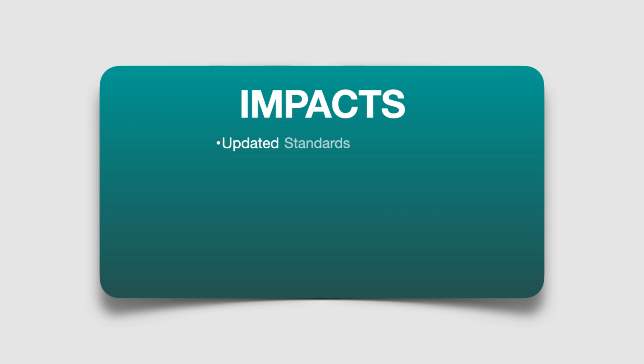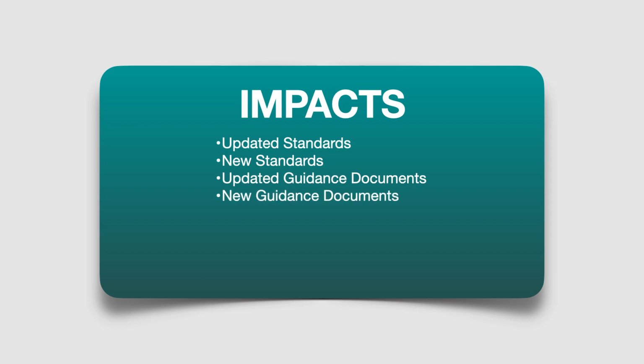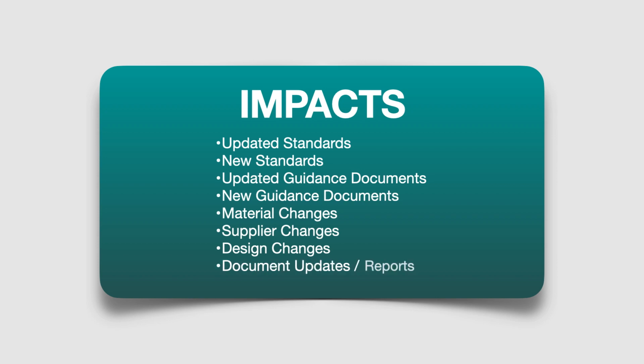As a manufacturer of medical devices, however, we must constantly prove conformity with Annex I. And there are constantly impacts that trigger proactive action. Standards are revised from time to time. Completely new standards come out which, as a manufacturer, I have to take into account. Guidance documents and best practices are also revised or newly introduced. The material used may change or the supplier announces changes. My own design changes, which I have initiated, for example, from observations after the product has been put on the market. And last but not least, the periodic updates of evidence documents, as required by MDR.